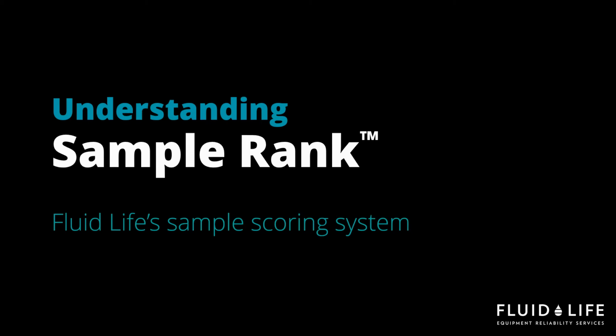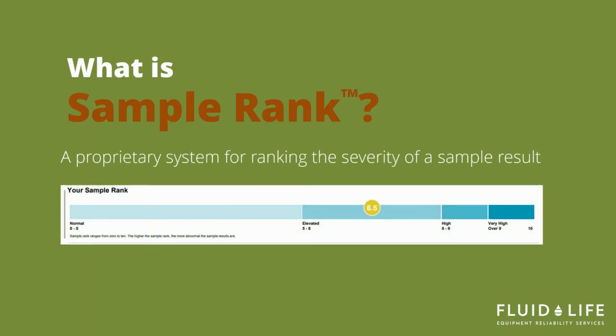In this video, we are going to discuss sample rank. Sample rank is a proprietary system for ranking the severity of a sample result. It's an informed estimate of how serious the problem is based on industry data and input from equipment owners. The sample rank can range from 0 to 10. The higher the sample rank, the more abnormal the sample results are.